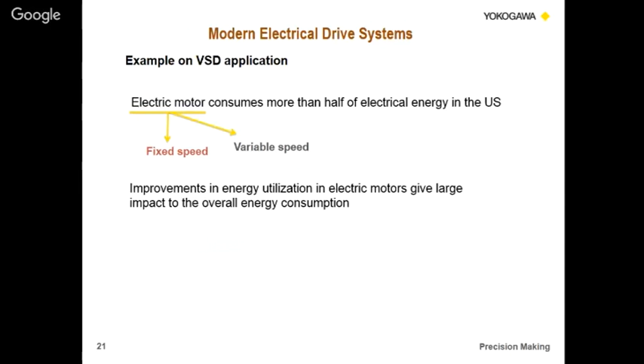But when you put a variable speed drive, if one person travels, the amount of power required to move that elevator is very small. But if 10% of capacity stands in that elevator, it requires more power. So the energy consumption in terms of the motor comes down if only one person stands in the elevator. Improvements in energy utilization in electric motors give a large impact on overall energy consumption, and the energy saving depends on the load.